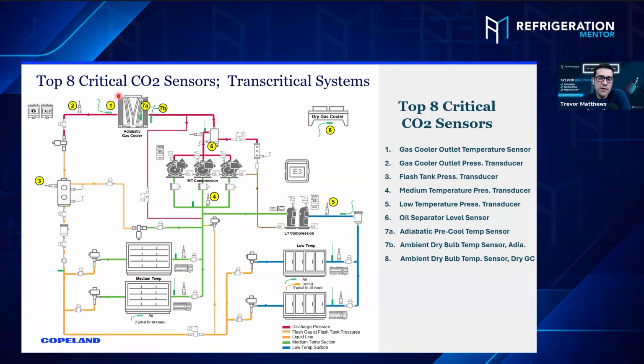What we're talking about here, if you're in a 90 bar system, your chances of losing refrigerant are going to be less, because in Europe the average is 60 bar, which is 800 and some psi. And then 90 is almost 1300, close to 1300 and a bit and change. And so when you start to get these higher pressure systems, which we'll start to see here in North America, we will not have to worry about relief events as much.